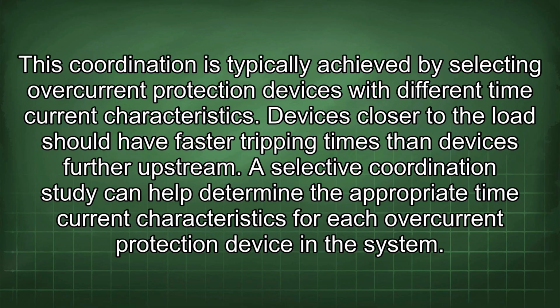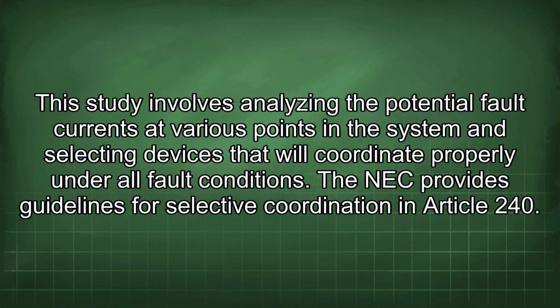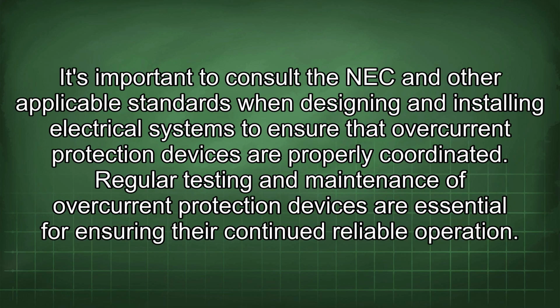A selective coordination study can help determine the appropriate time current characteristics for each overcurrent protection device in the system. This study involves analyzing the potential fault currents at various points in the system and selecting devices that will coordinate properly under all fault conditions. The NEC provides guidelines for selective coordination in Article 240. It's important to consult the NEC and other applicable standards when designing and installing electrical systems to ensure that overcurrent protection devices are properly coordinated.